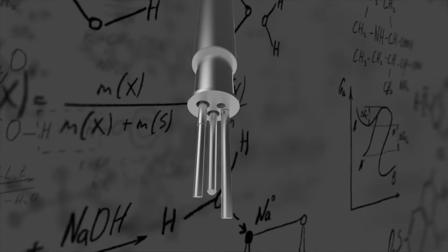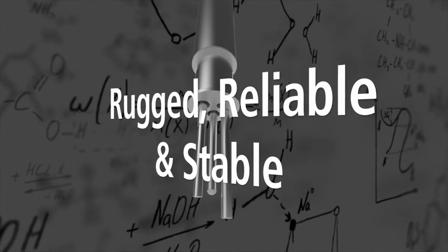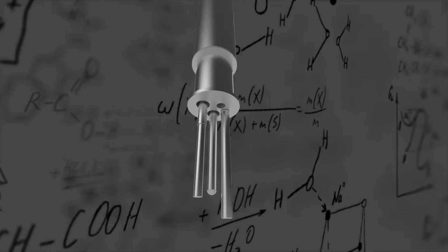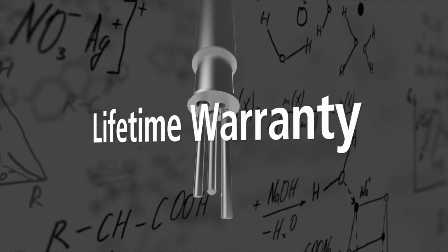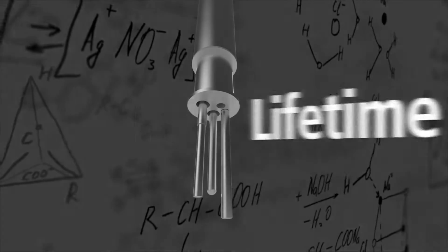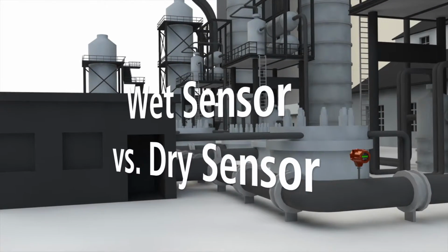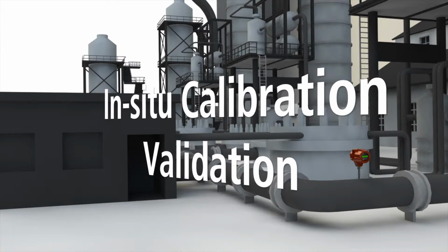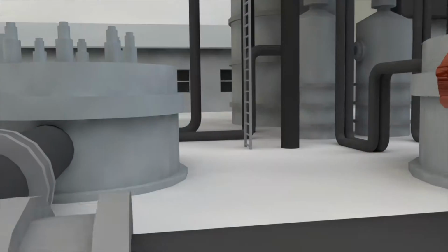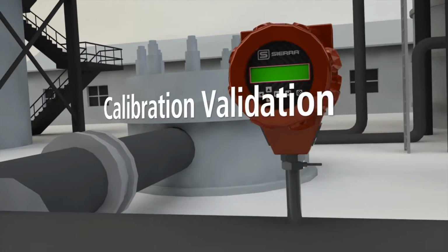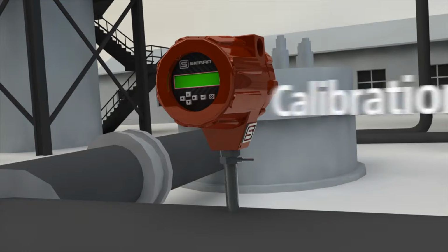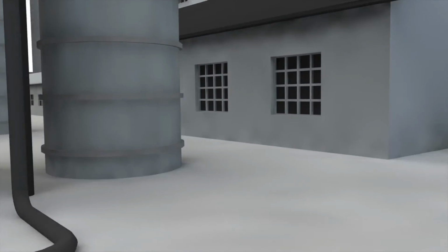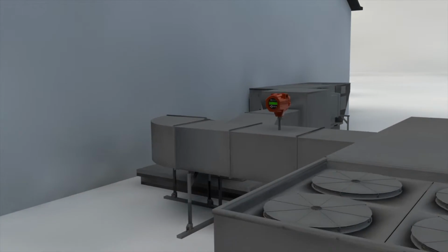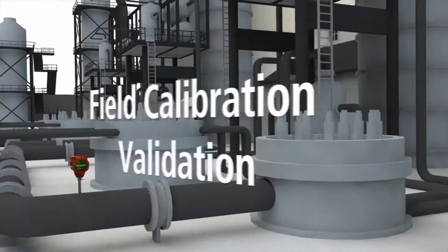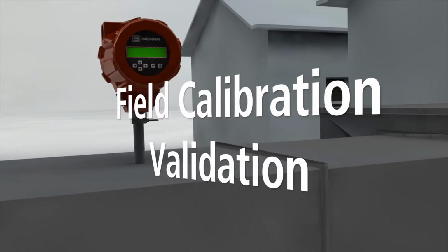Because the all-metal DrySense sensor is so rugged, reliable, and stable, Sierra has backed quality claims to be the only company in the industry to offer a lifetime warranty on their thermal sensor. With wet sensor versus dry sensor design in mind, let's briefly discuss in-situ calibration validation. Quality systems, like ISO 9000, may require annual or even semi-annual calibration and validation of all measurement instruments in a facility. One of the nice features of thermal mass flow meters is that the calibration can be easily validated in the field at a very low cost.